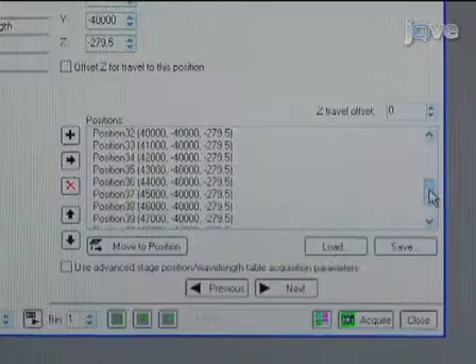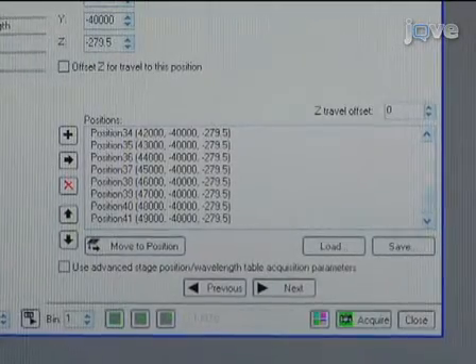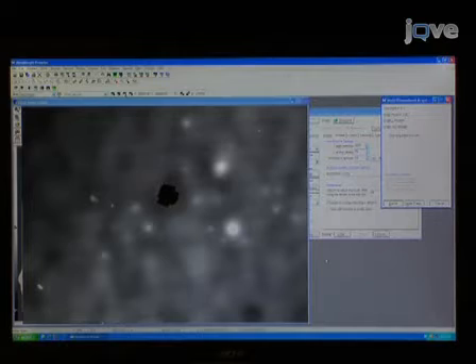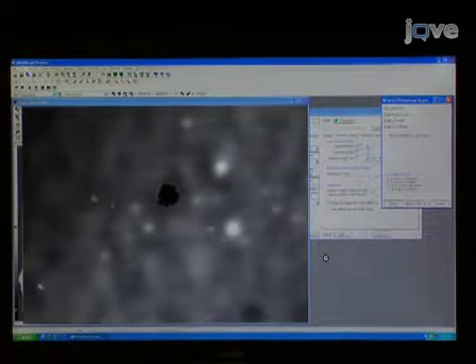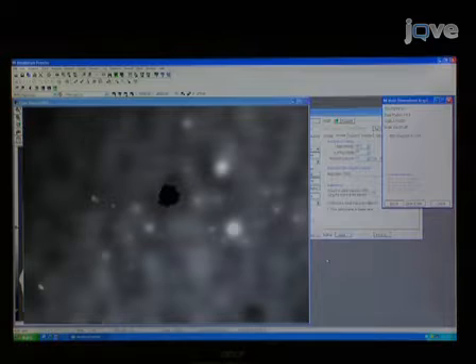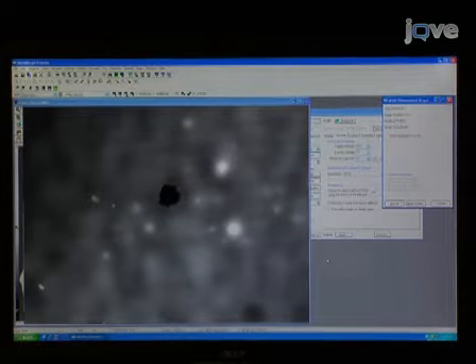To test for equilibration time and extent of oxygenation for the device, choose 3 points on the Foxy slide in which to measure the oxygen concentration. Capture an image of the slide immediately before starting the flow of gas. Capture images in intervals of 10 seconds over 30 minutes as the gas flows through the device.